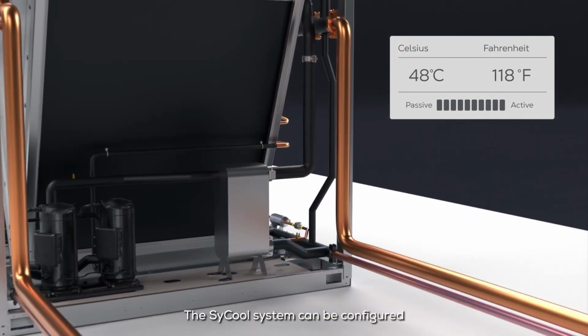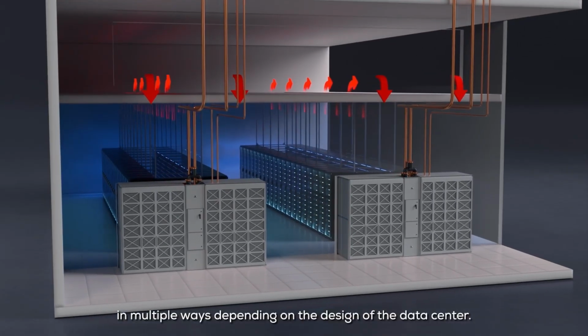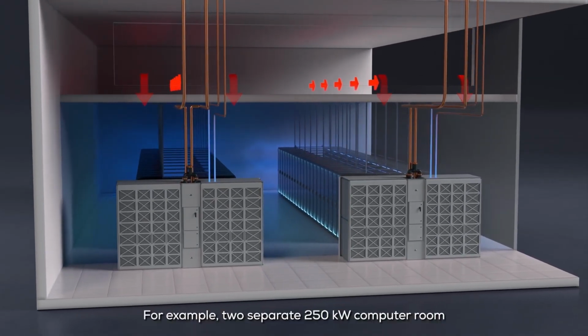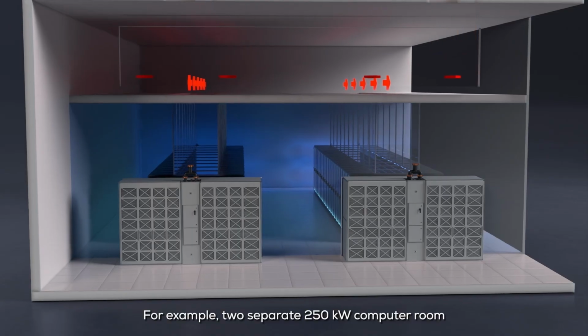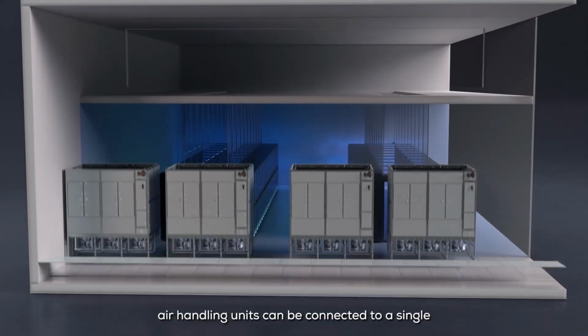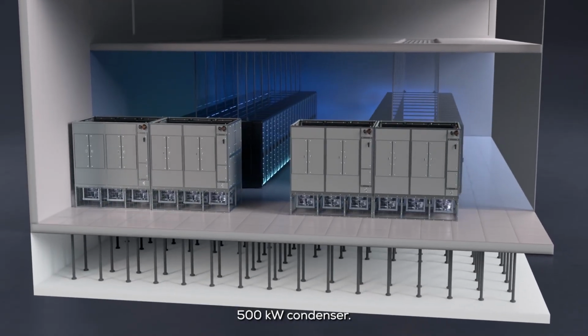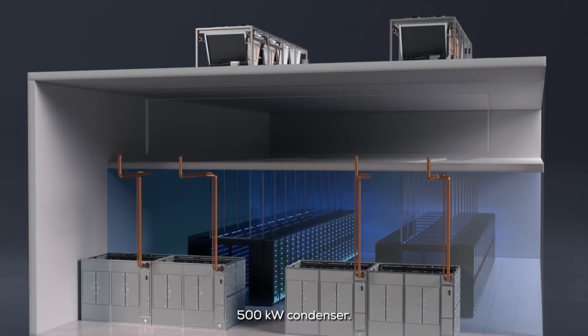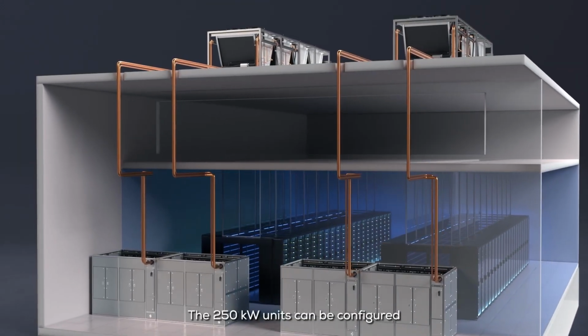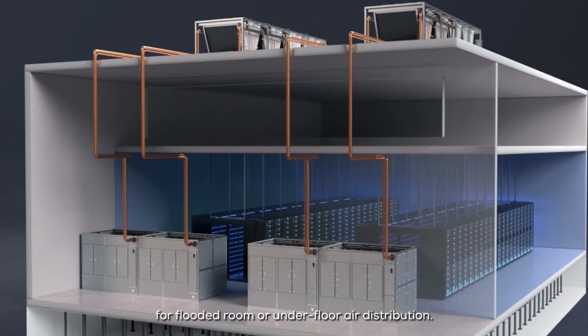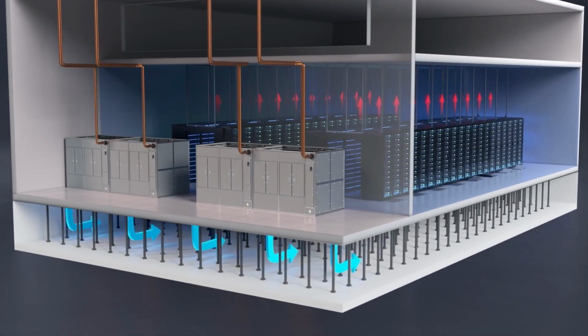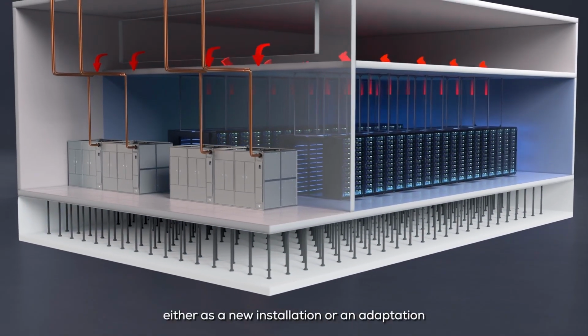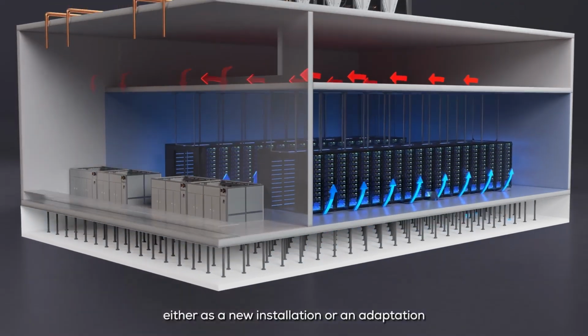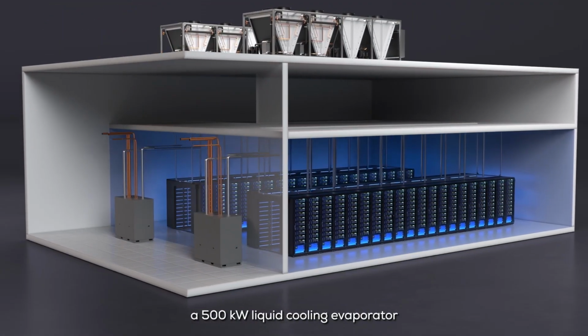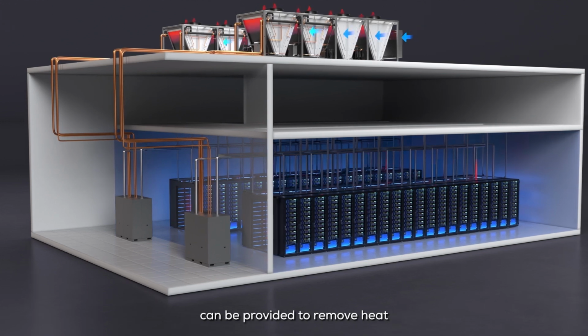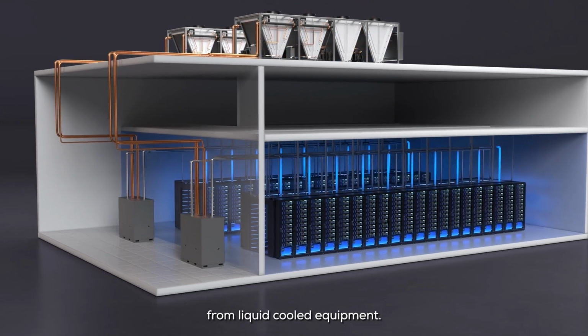The SyCool system can be configured in multiple ways, depending on the design of the data center. For example, two separate 250 kilowatt computer room air handling units can be connected to a single 500 kilowatt condenser. The 250 kilowatt units can be configured for flooded room or underfloor air distribution. If liquid cooling is required, either as a new installation or an adaptation from an air-cooled system, a 500 kilowatt liquid cooling evaporator can be provided to remove heat from liquid-cooled equipment.